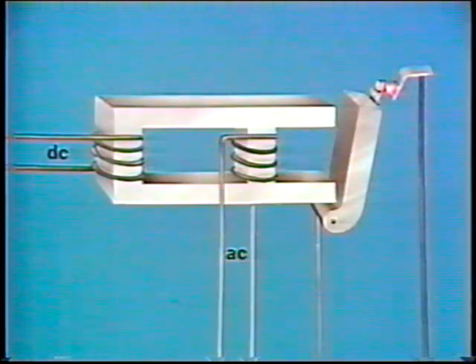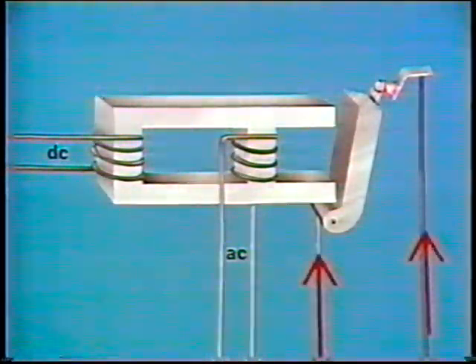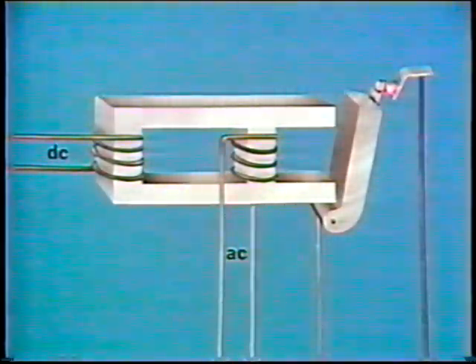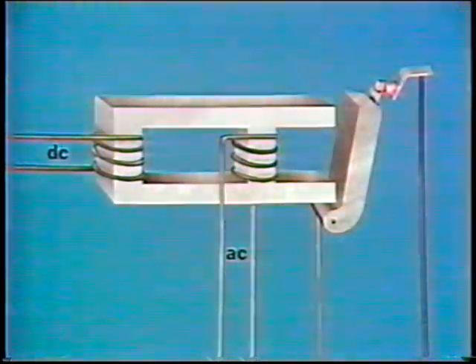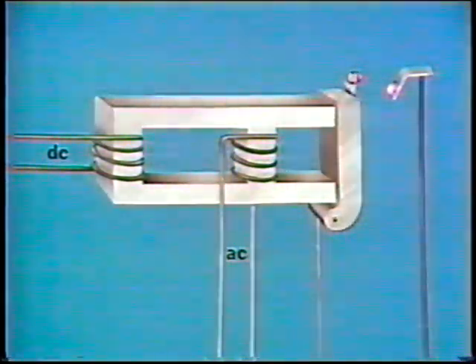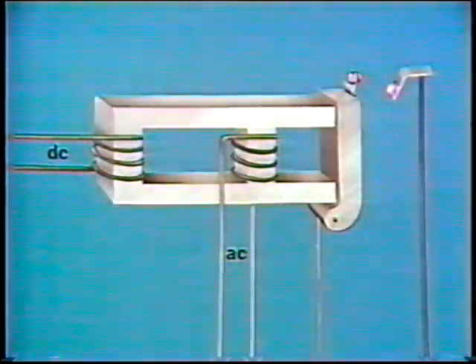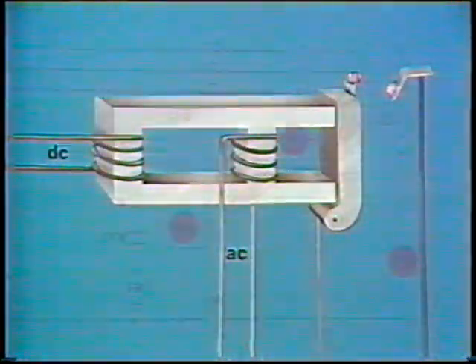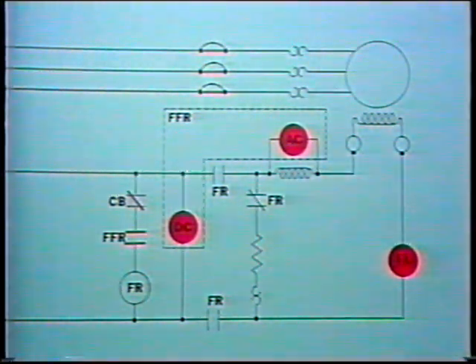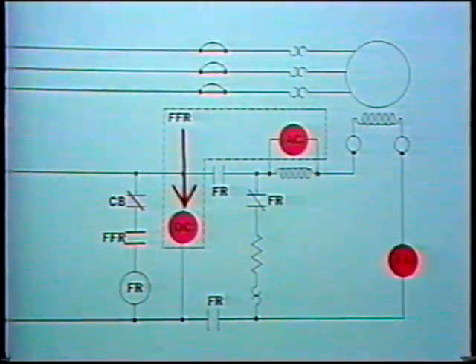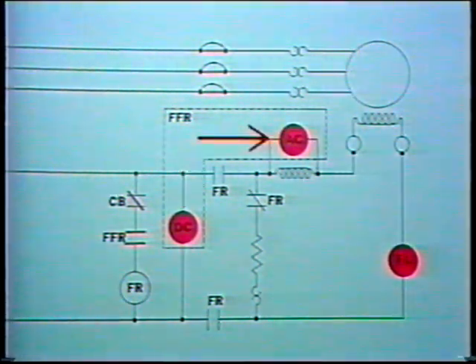This drawing shows a typical field frequency relay. The relay has 2 coils wound around a core. Its contacts, which are connected to a circuit by these wires, are normally in a closed position. When both coils are energized, the contacts of the relay open and break the circuit. Neither one of the coils alone can open the contacts of the relay. Both coils must be energized before the contacts will open. In the control circuit, the field frequency relay is placed so that one of its coils is connected across the DC power supply. This coil is known as the relay's DC coil, and it continually receives a supply of direct current from the DC power supply. The relay's other coil is connected in parallel with the inductor in the circuit.